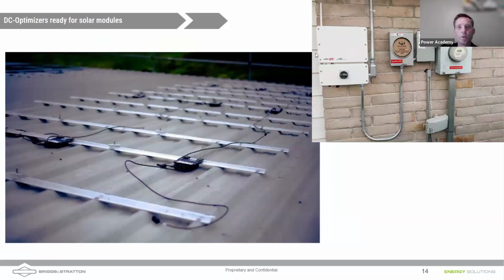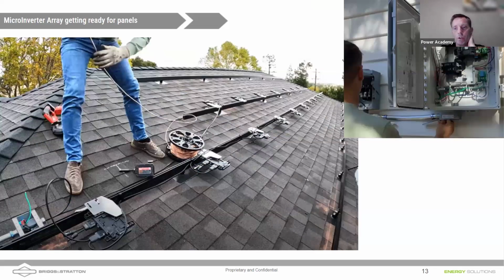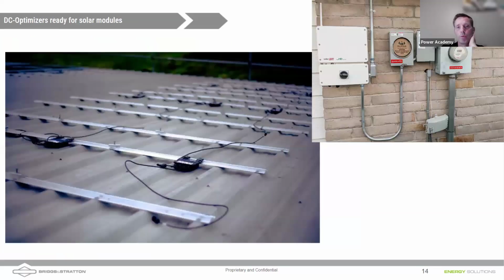Here is an example of a SolarEdge system with DC optimizers already on the roof, ready to have the panels plugged into them. These optimizers will work differently than the Enphase microinverters. These will keep the power DC, but these have DC to DC converters in them and essentially act fairly similar to an MPPT, a maximum power point tracking device. And you can see that power coming down the side of the house. This looks like a SolarEdge 7600, and that's got a disconnect. And those optimizers also act as rapid shutdowns in the same way that the microinverters you saw here will act as rapid shutdowns. So unlike with a DC system where you just have solar panels and you're required to have accessories as rapid shutdown devices, both of these sets of devices will work as rapid shutdowns in the event of a grid down situation.